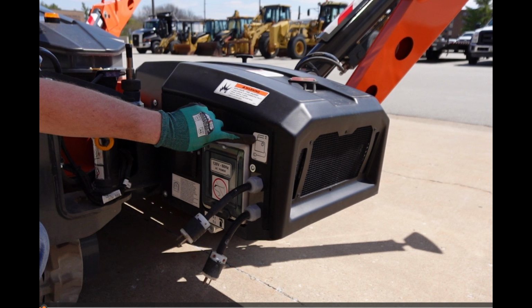The charger cord and power to platform cord are both located at the platform end of the machine next to the breakers. The charger cord is the uppermost cord, denoted by the decal above. The power to platform is the lowermost cord. When charging, the battery monitoring system, or BMS, is constantly monitoring each lithium cell and balancing out the charge to the lithium pack. Plugging in the charger initiates the BMS. If the machine is left plugged in for long periods of time, the BMS will actually discharge the battery. Do not leave the X660 plugged in for periods longer than 24 hours.